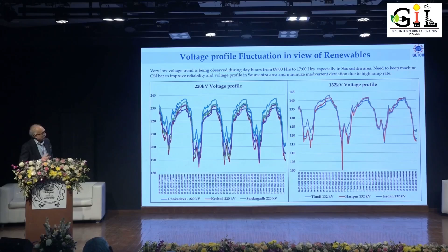We have captured the data of three particular stations where agricultural load is dominant. You will find that in the daytime, when solar is at maximum, at that point of time voltage is minimum, beyond the limit of the grid code, sir. In between, there is a jump from 190 to 200. During the recess time, at 12 to 1, voltage is recovered, and then after that it goes down below 190. So this is a scenario specifically in our Saurashtra areas, at three 220 kV substations and three 132 kV substations. Everywhere you will find voltage is beyond the limit of the grid code.